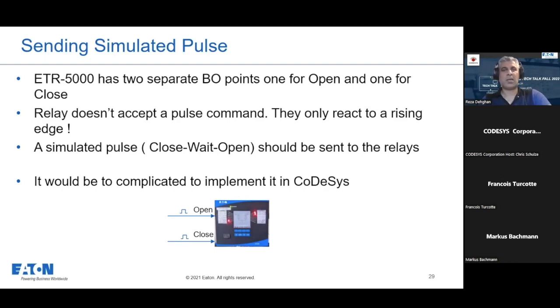So every time we want to send an open close command to the relay, the general, easy way is just to send a binary command. There are two ways. You can send one binary output, 0 for open, 1 for close, or you can have two separate points, one for open, one for close, and then you send a pulse on open, it will open the breaker. You send a pulse on the close point, and it will close. But the relay doesn't really accept a pulse command. They only react to a rising edge, which was a little bit strange.